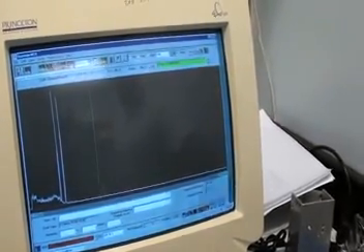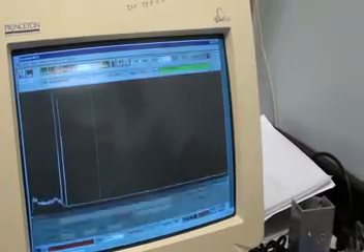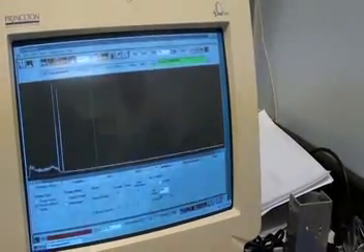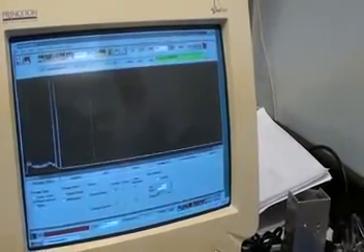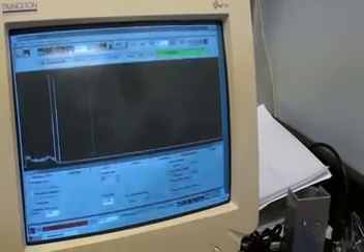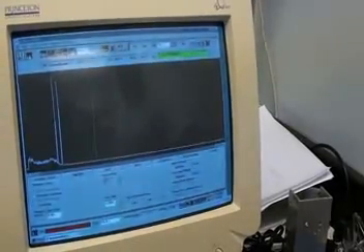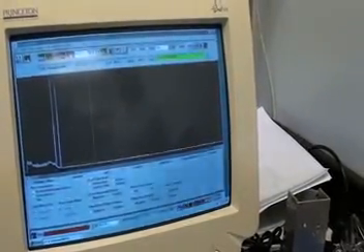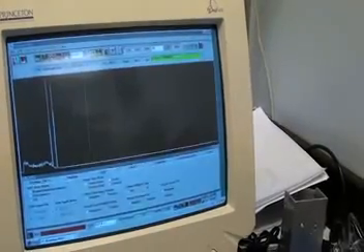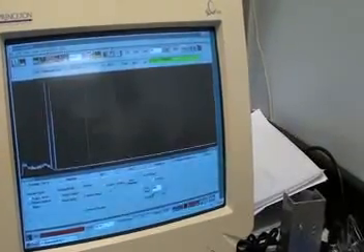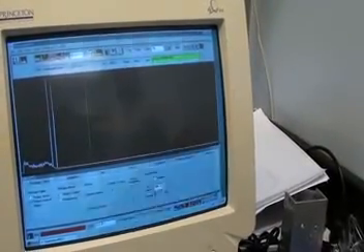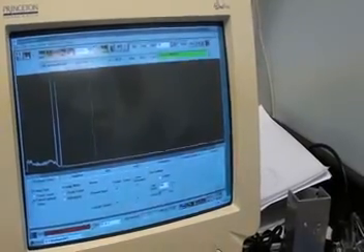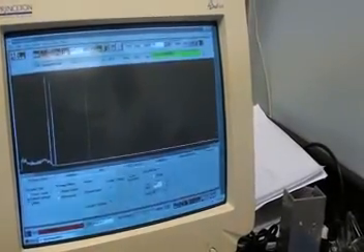This button here — the spectrum info — allows you to change the menus and get to the bottom where you can access the bias, amplifier, and ADC information. For our purposes we are looking at the bias. Usually we will start at 500 volts and slowly increment it up from there.